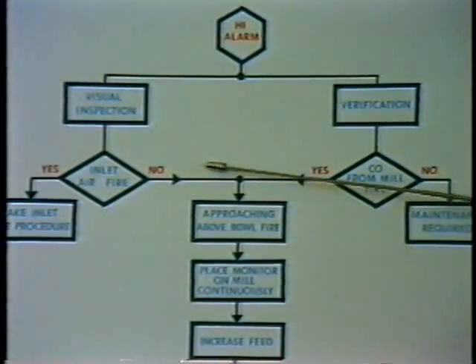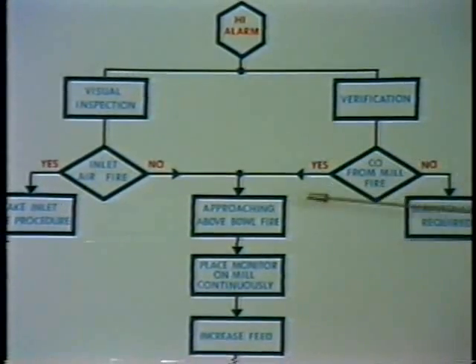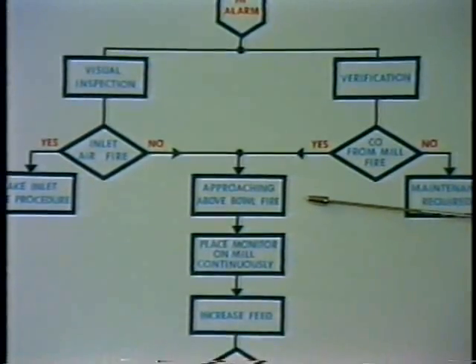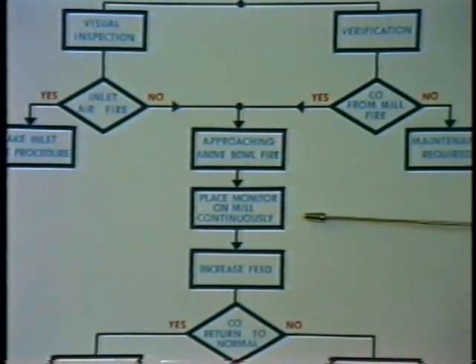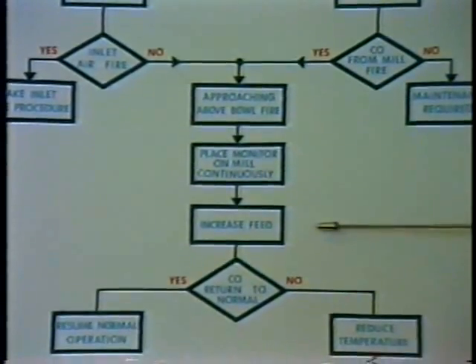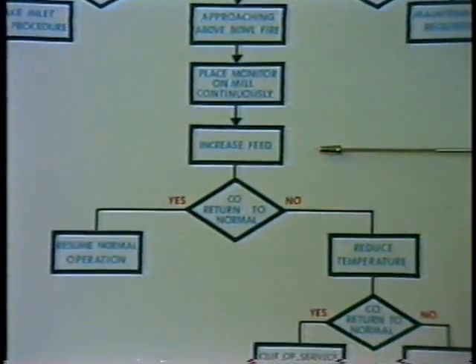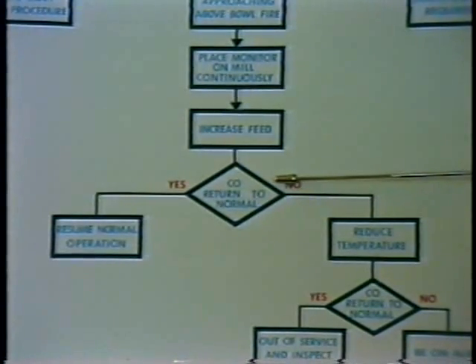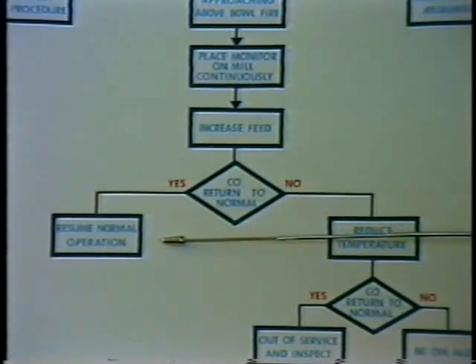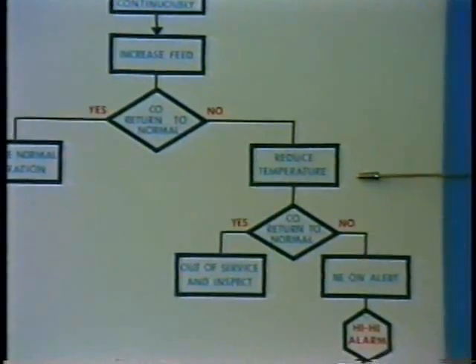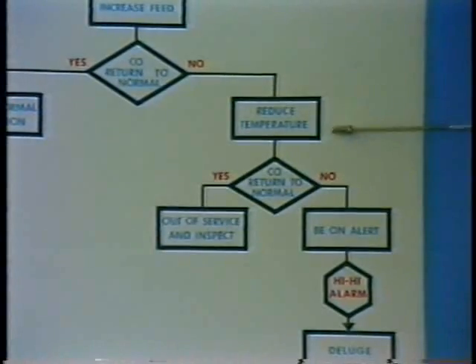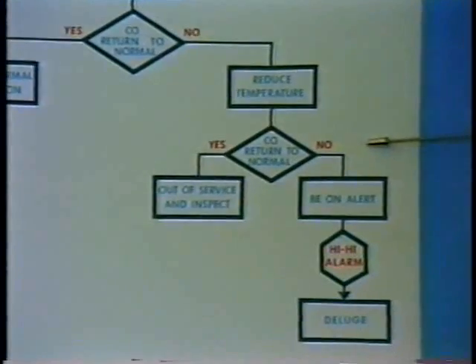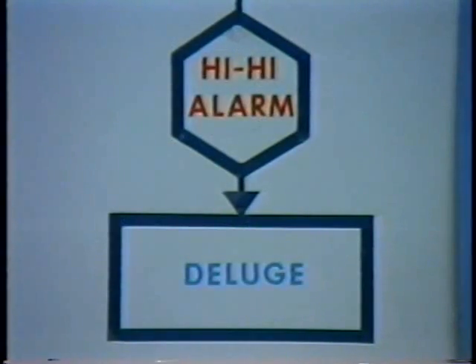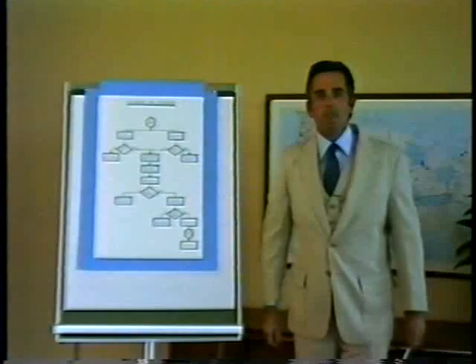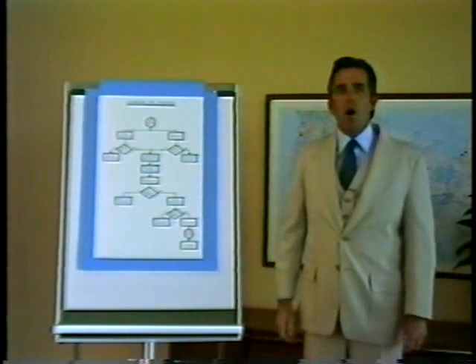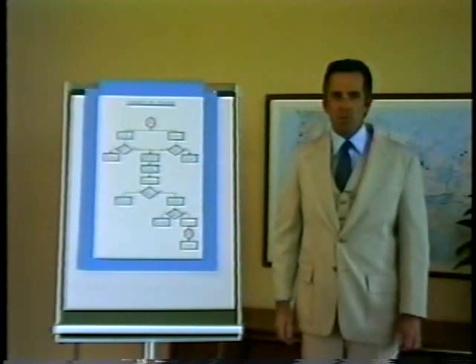If there is no inlet air fire and there is carbon monoxide coming from the mill, they operate on the presumption that they are approaching an above-the-bowl fire, in which case they place the monitor on the mill continuously and increase the feed to the pulverized coal system. After increasing the feed, they watch to see if the carbon monoxide returns to normal. If it does, they resume normal operation. If not, they reduce the outlet temperature of the mill to see if the carbon monoxide returns to normal. If it does not, they are on alert, and in the presence of a hi-hi alarm, they deluge the pulverizer system.